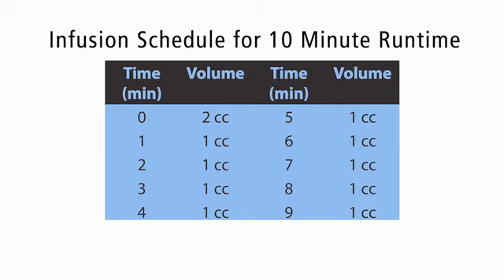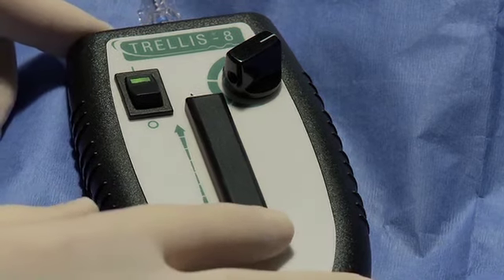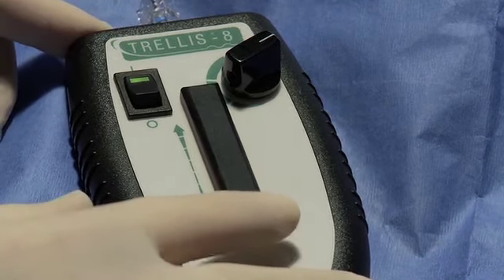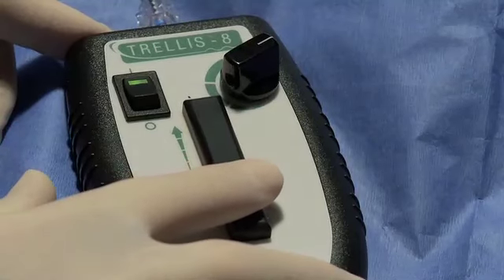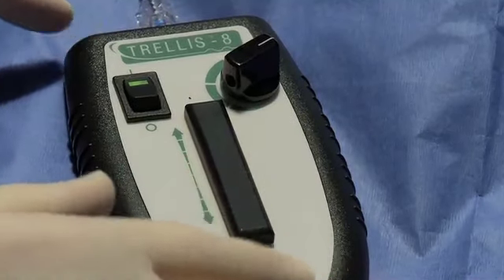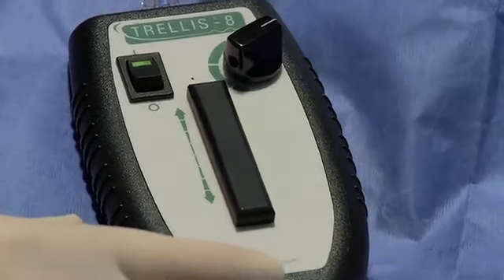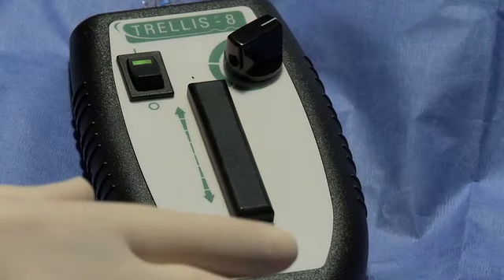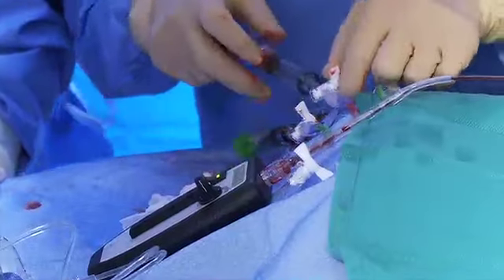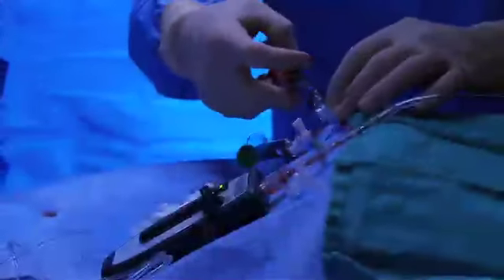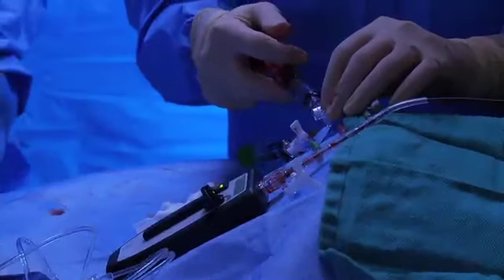Adjust appropriately. Utilize the translation bar to achieve dispersion of the infused fluid by slowly repositioning the translation bar fully following each infusion, or approximately once per minute. Do not translate the dispersion wire more than once per minute. Continue to infuse the physician-specified fluid using the stepped infusion schedule.